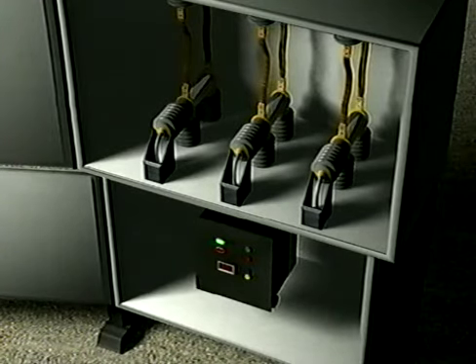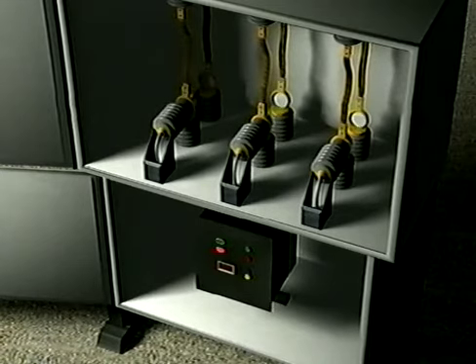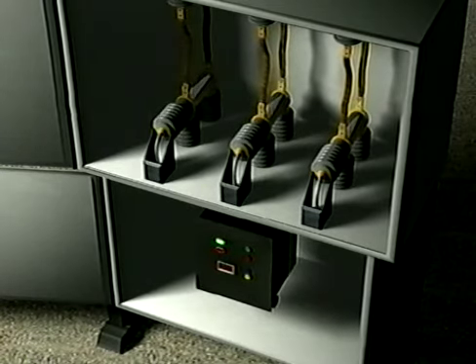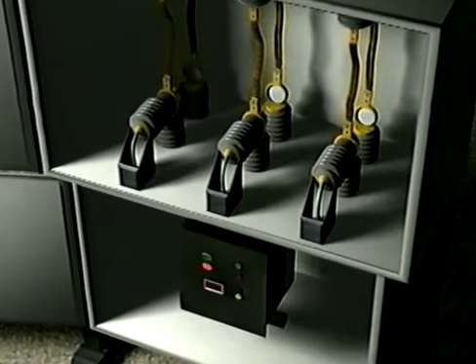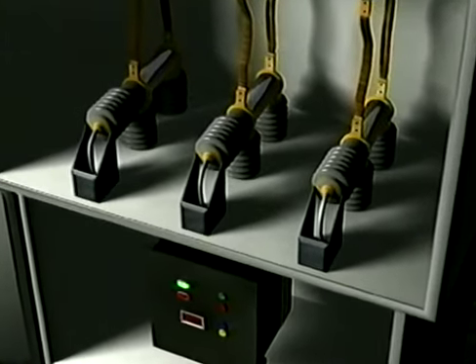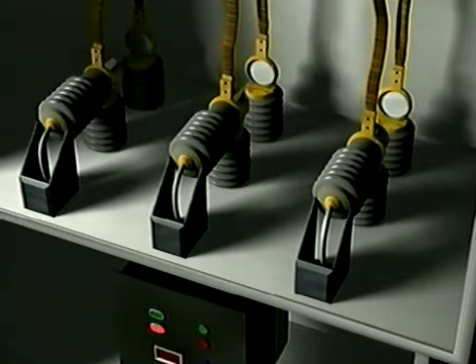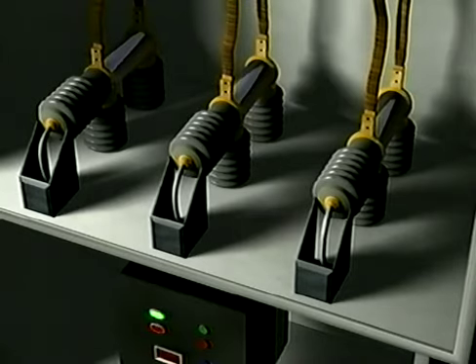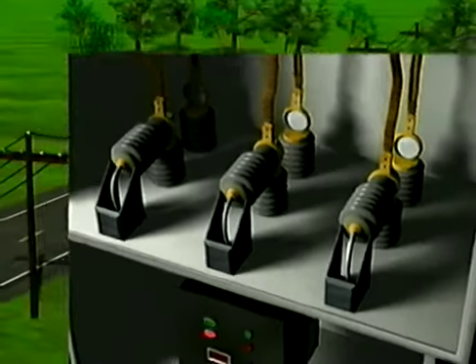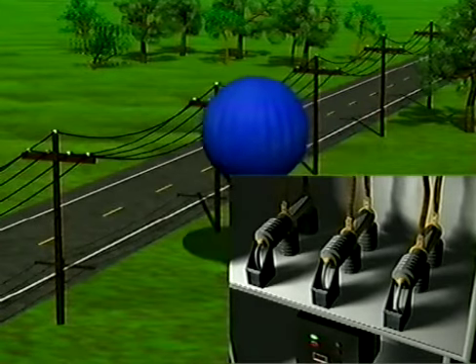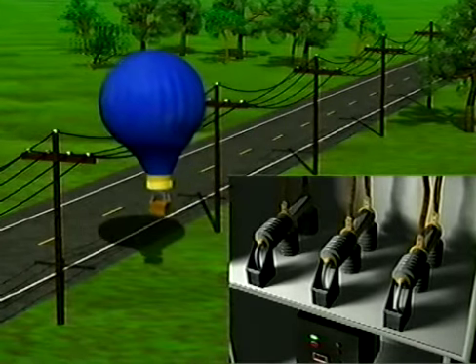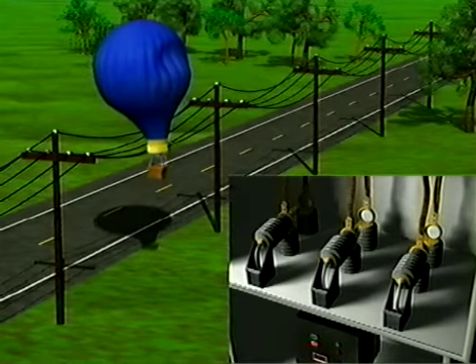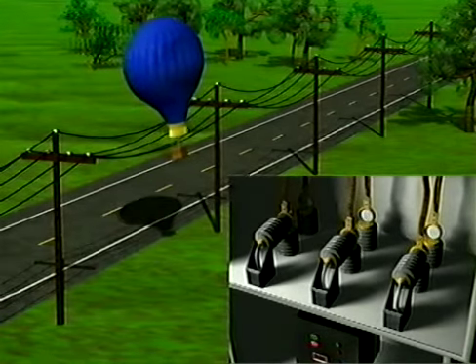Unfortunately, for balloonists caught in power lines, many circuit breakers automatically reset because many faults in the field are momentary faults. Rather than disrupt a large portion of the service area that could cause a blackout, the circuit breaker assumes the fault will last only a short amount of time and therefore will automatically reset to restore power to the area. For a balloon sitting in these wires, the circuit may open, thus de-energizing the line, perhaps multiple times before locking in the open or safe position.